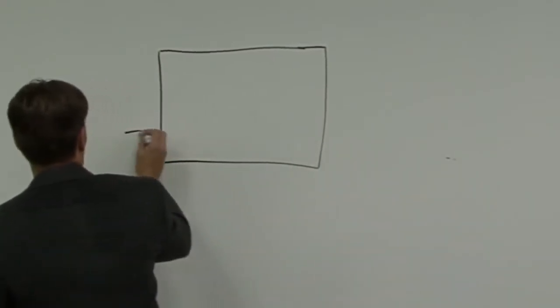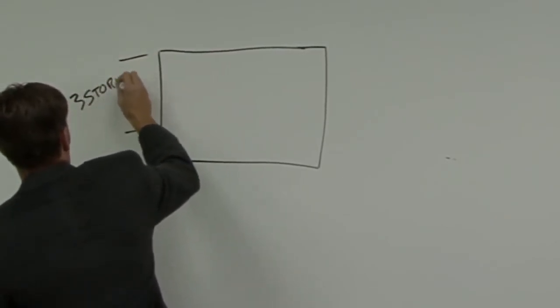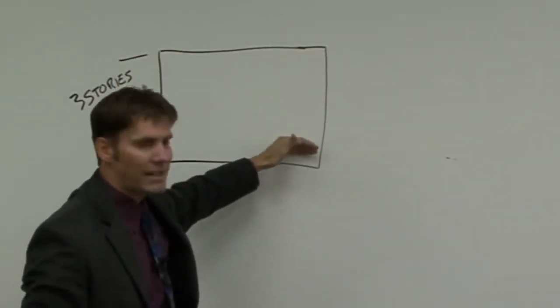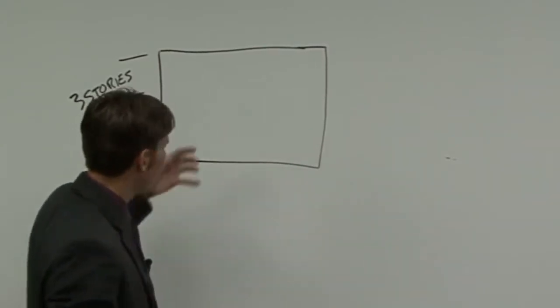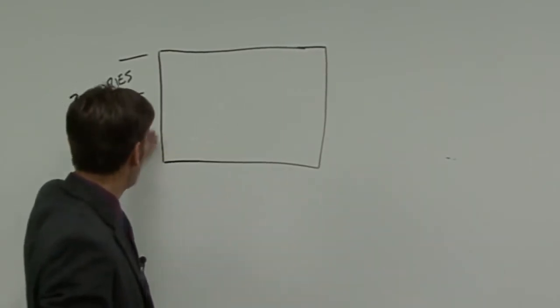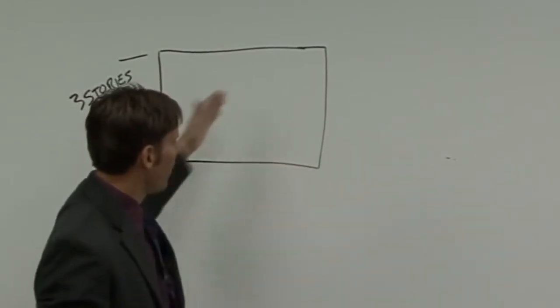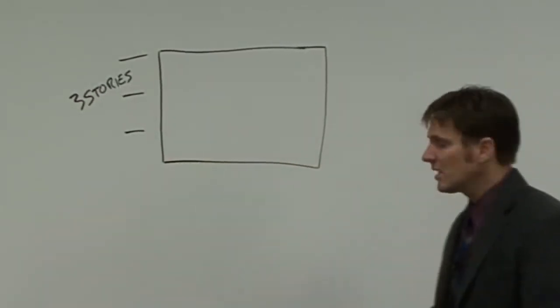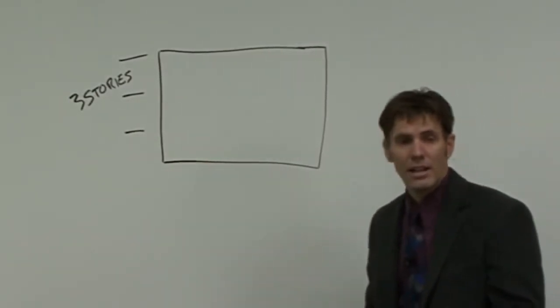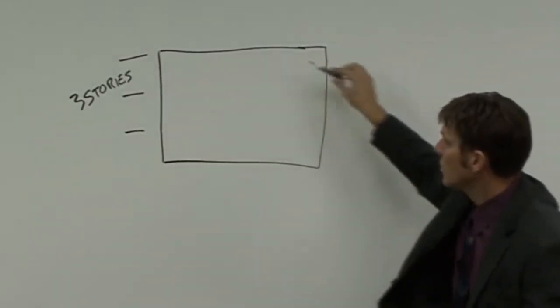We might have to lift up 3 stories in a building. But when I have to lift that water, I also have the weight of that water back down in this closed loop system. So when we size a pump or when we put something in here to move the water, I don't have to move that water up because that water is moving itself down. So when I want to move flow in a hydronic heating or cooling system, we're using water or a liquid, maybe it's a propylene glycol solution or some type of water solution that we're going to heat and cool this building.